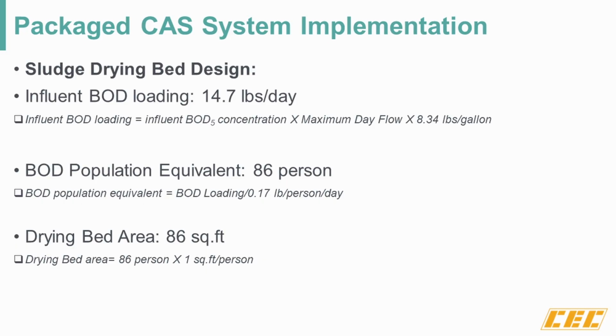We also designed the sludge drying bed, and these are the primary calculations that we used to design the sludge drying bed. So based on the influent BOD parameter that we determined through sampling in the influent wastewater, we calculated the BOD loading. That is dependent on the influent BOD5 concentration, the maximum day flow, and a conversion factor associated with it. Once we determined the influent BOD loading, we used that to determine the BOD population equivalent, which we need to finally determine the drying bed area for the package plant.